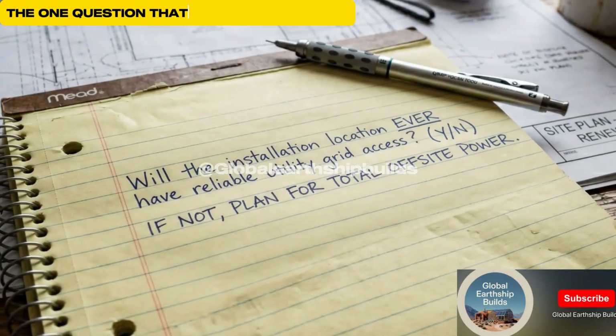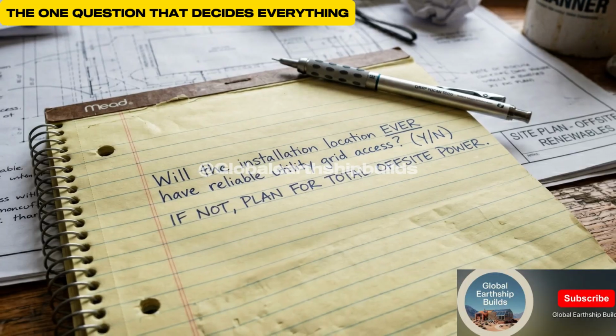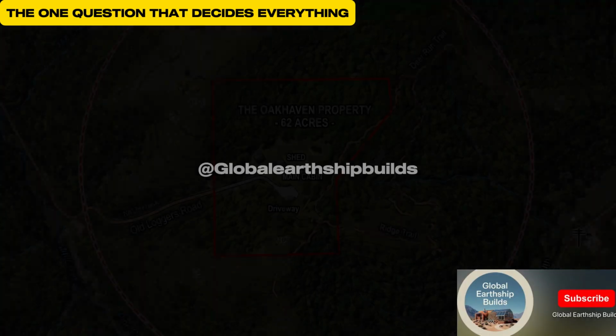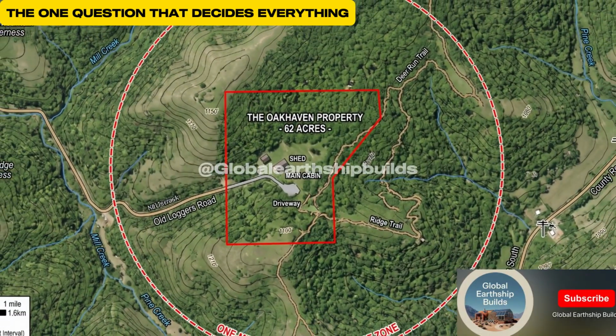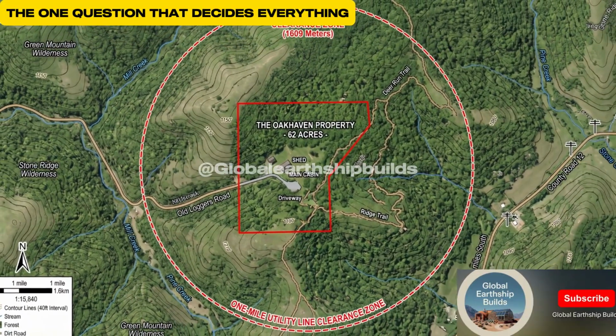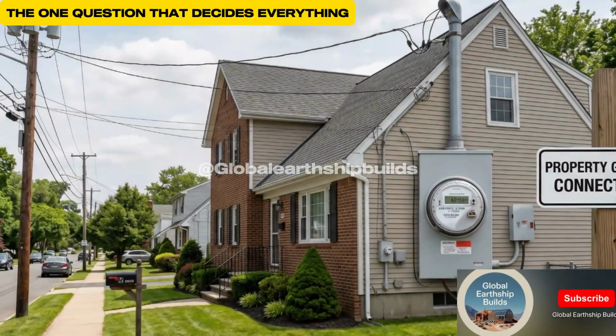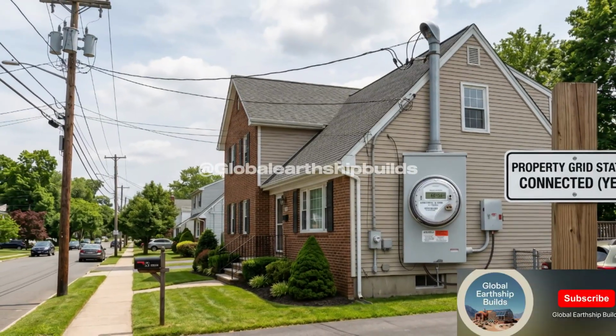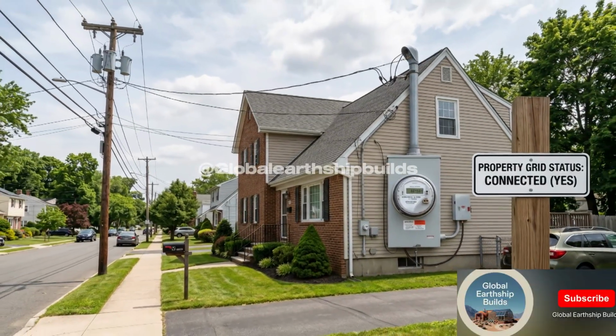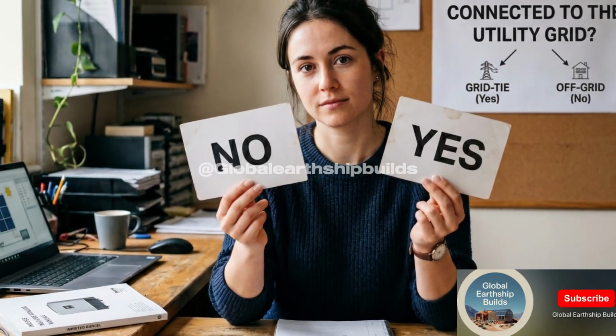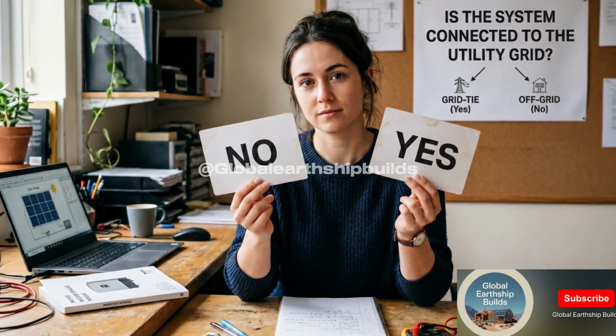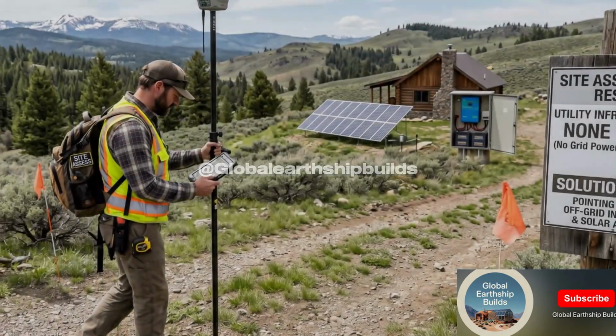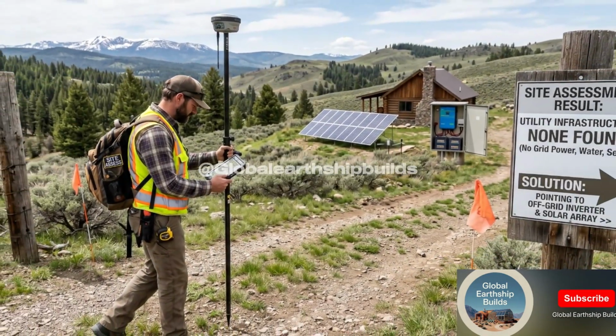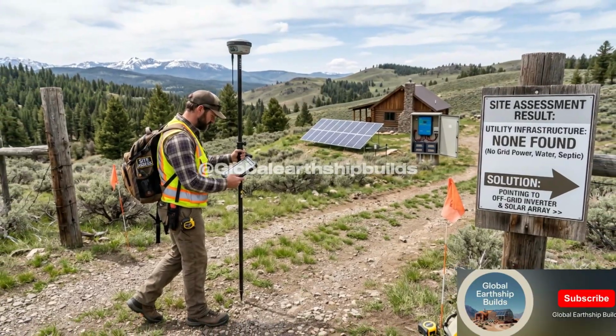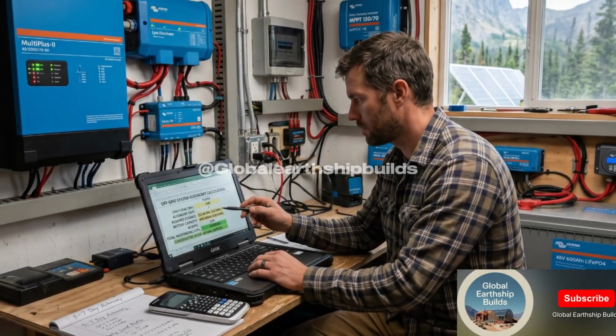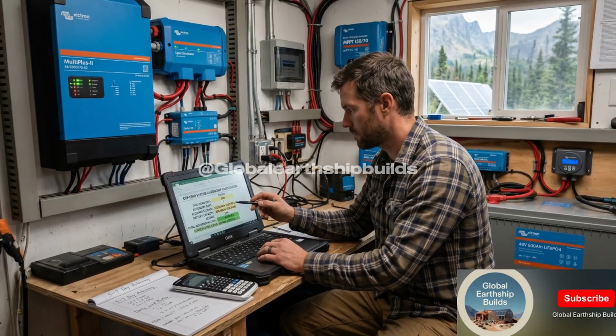The one question that decides everything: after all of that, here is how to make the decision simply. Ask yourself one question: will this system ever be in a location with reliable utility grid access? If the answer is no, you are off-grid by definition. Optimize for that. Get the inverter with the best surge capacity, the deepest integration with your battery bank, and the generator compatibility you need. Victron or Outback. Size your battery bank for 5 to 7 days of autonomy, minimum, depending on your climate.